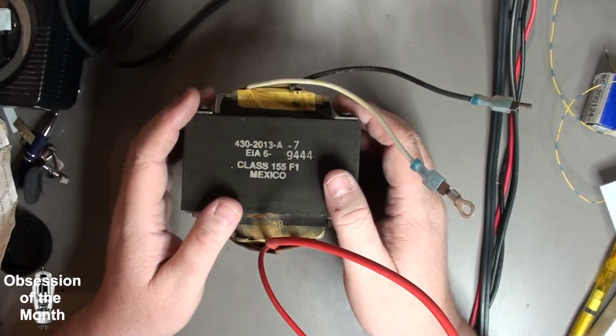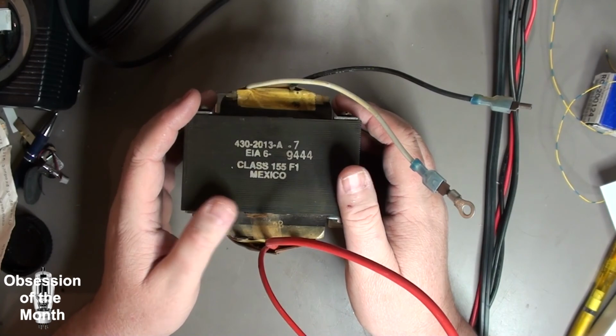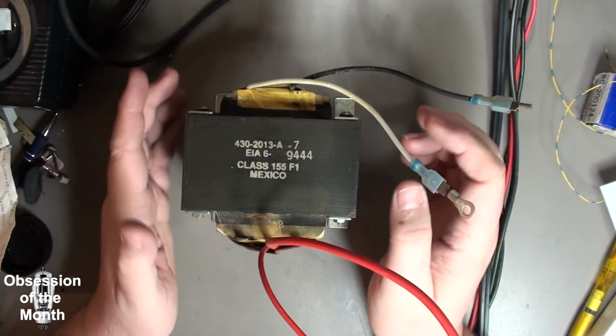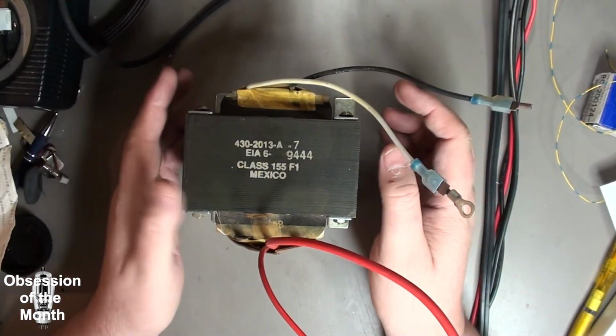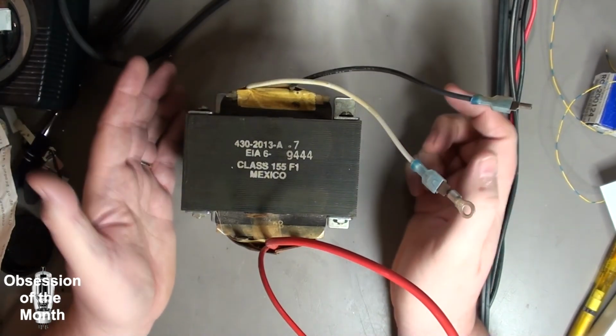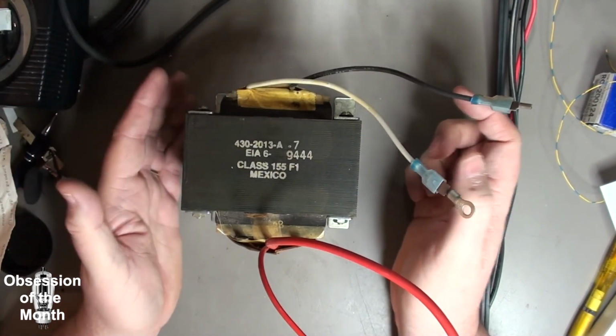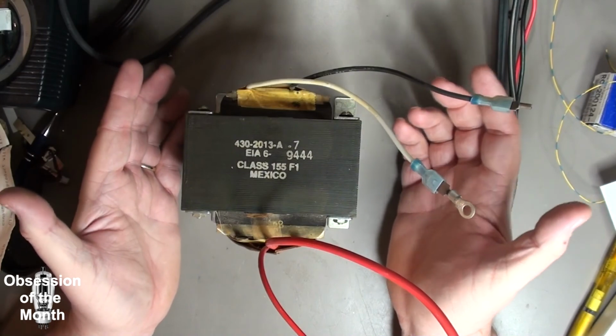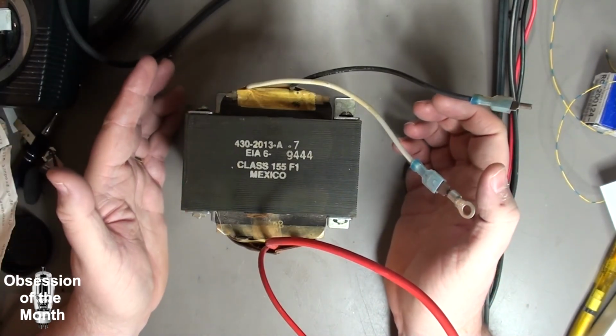If you find the wiring is rated 10 or 15 amps max, you'll want to set a current limit lower — if it's 15, maybe limit to 10, and if it's 10, limit to 8, that kind of thing.